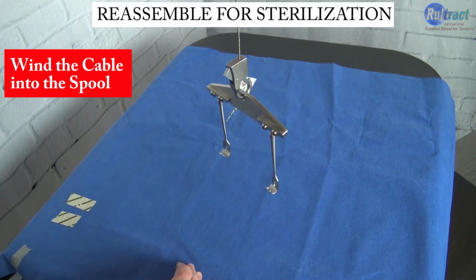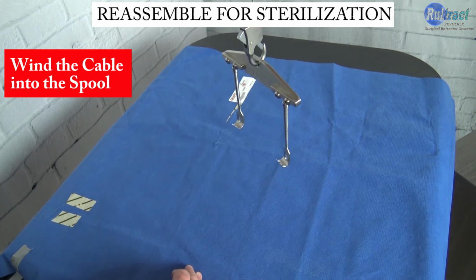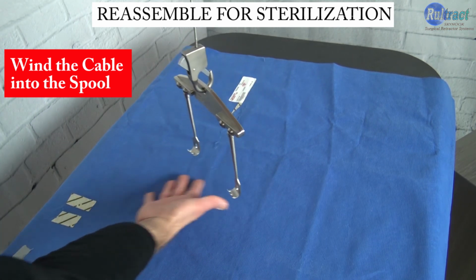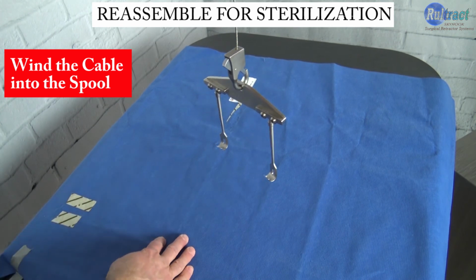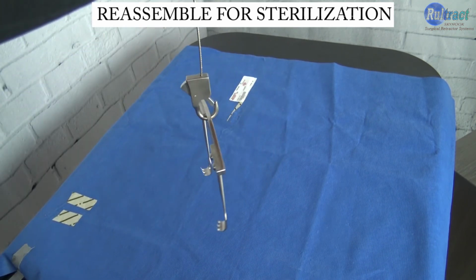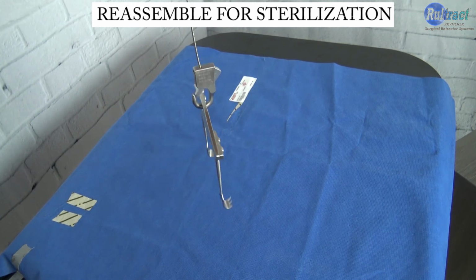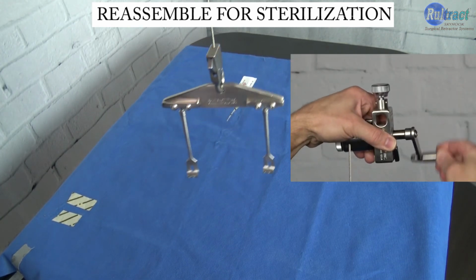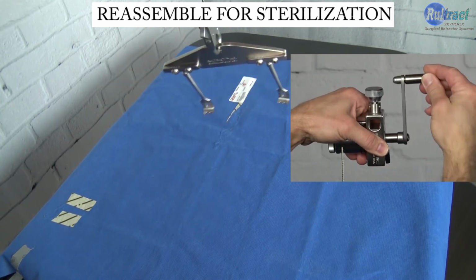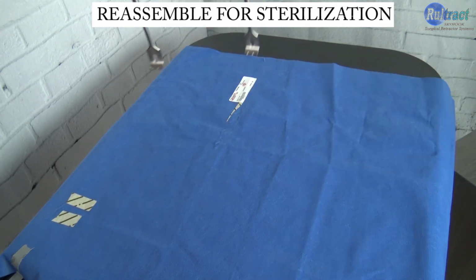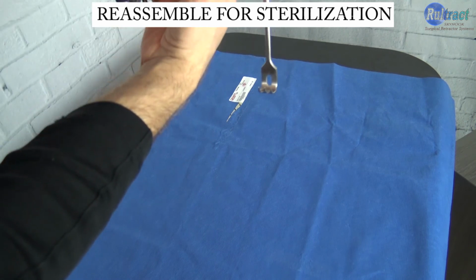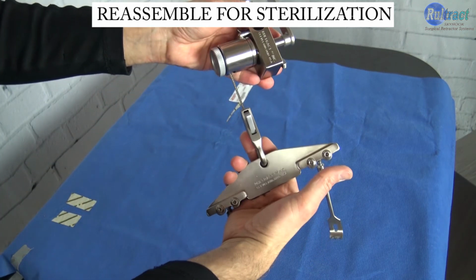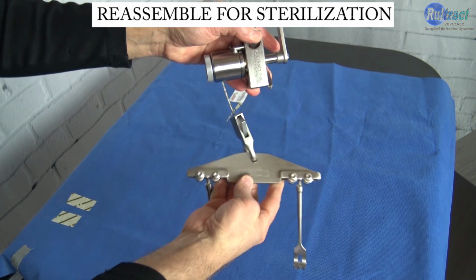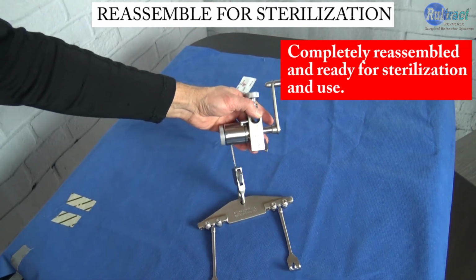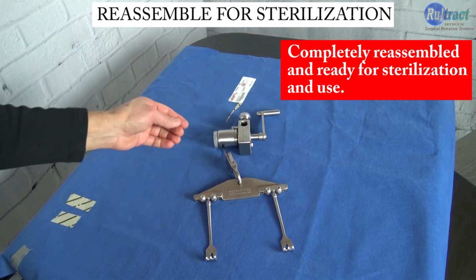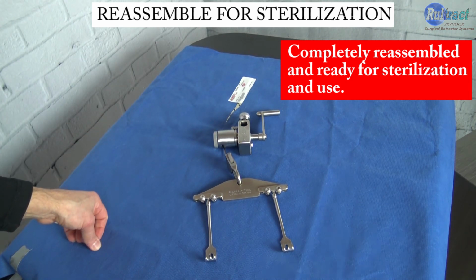So what you want to do is to stand up at your desk, hold the ratchet assembly up in the air high enough so that the rake plate is suspended above the desktop. Then go ahead and wind the cable into the spool. You should leave about 2.5 to 3 inches of cable exposed. Now your Rultract ratchet rake assembly has been completely reassembled and ready for sterilization and use.